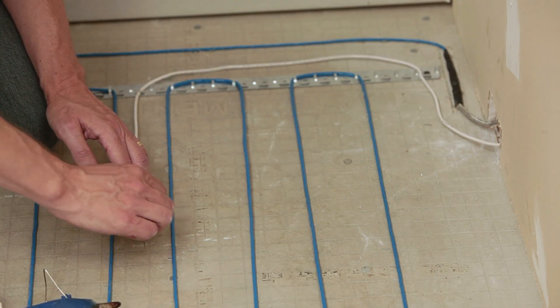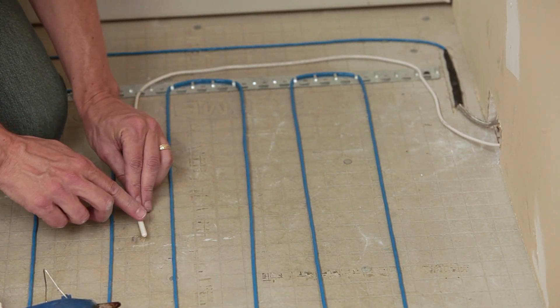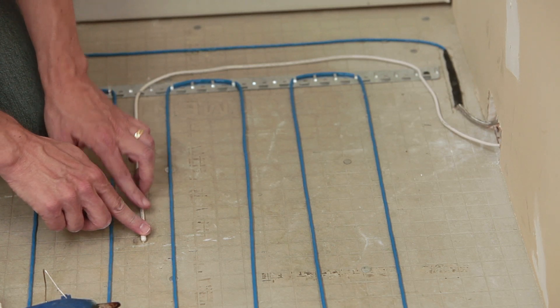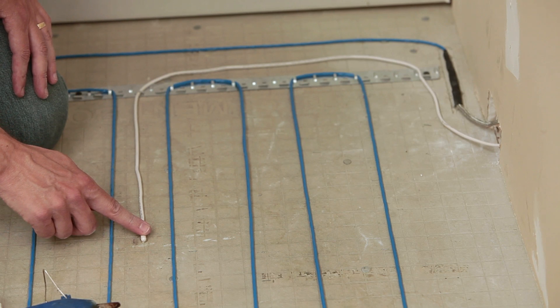Position the floor sensor parallel to and in between the heating elements. Do not run sensor wire across heating elements. Attach the sensor to the floor with a small amount of hot glue.